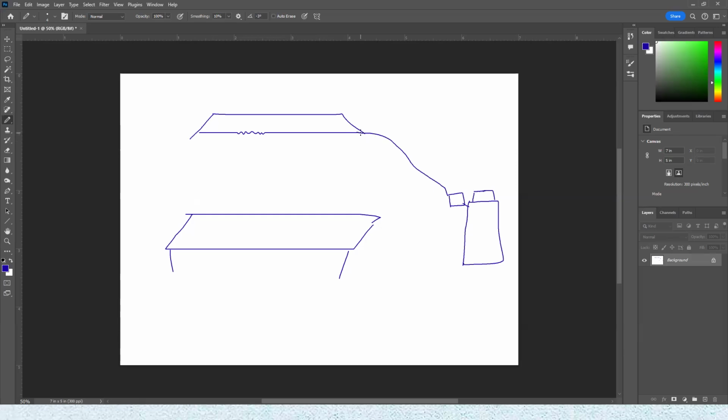That steel wire, like a piano wire, you can buy at the Home Depot, for example, or Rona, or other home hardware. It's under constant tension. If that tension breaks, the trigger triggers that. And that piano wire or aircraft cable or steel wire has to be installed in rigid, usually half-inch pipes.